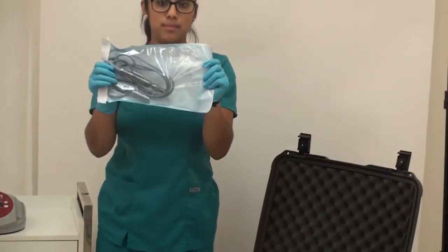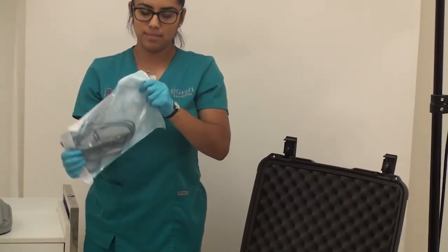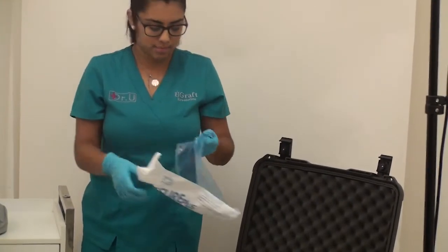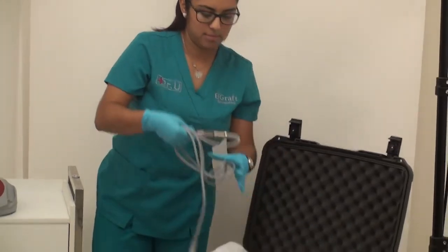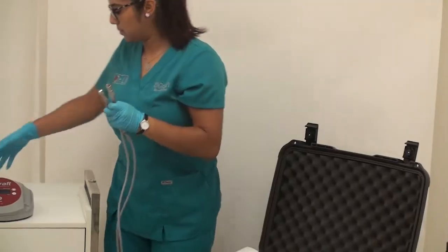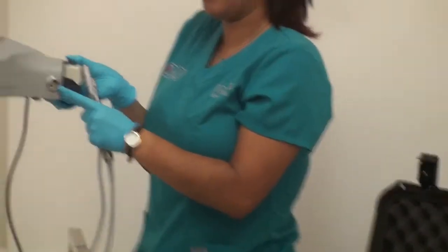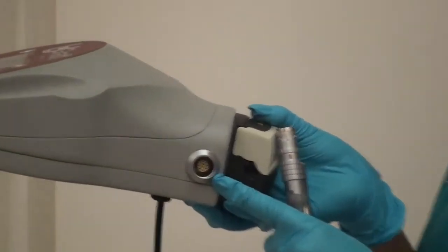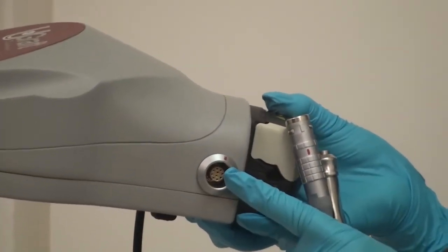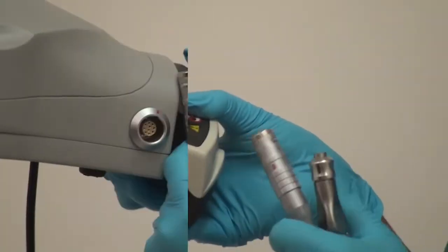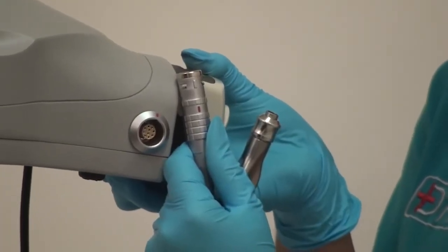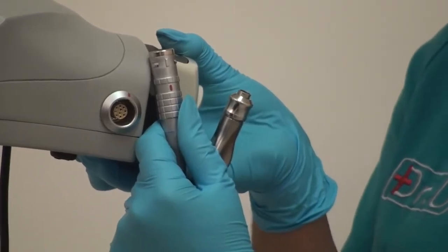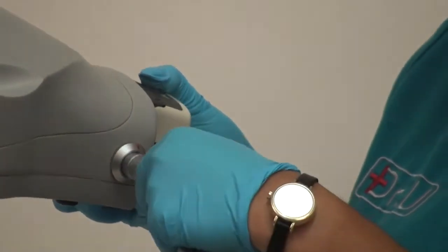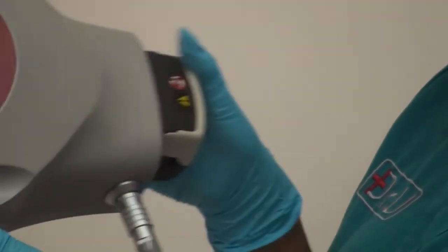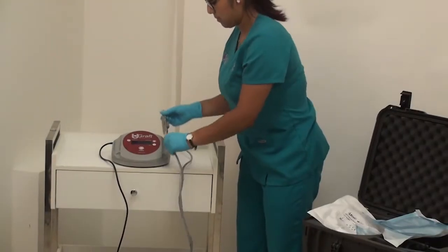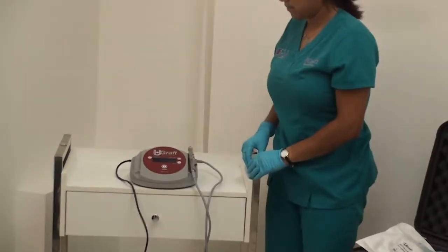Next, you will need to connect the handpiece, which you have already sterilized, so you'll need to take it out from the sterilization pouch. First, connect the handpiece cord to the port on the right-hand side of the console. There is only one port on the right-hand side of the console, which has a red dot on the 12 o'clock position. There is a red dot on the handpiece cord. Align it to the red dot on the console, and then push it in until it snaps. You can place the handpiece on the port to the left side of the console.